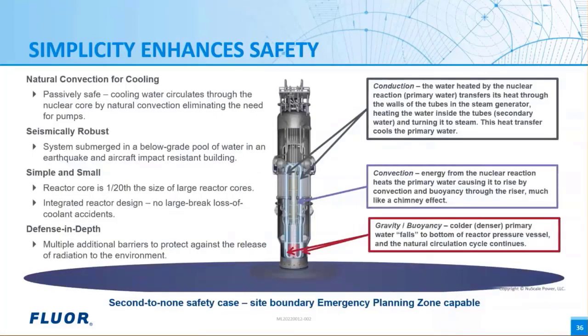So why is this reactor so safe? The safety is in the simplicity of the design. As I said previously, there are no pumps. It works entirely via natural circulation. The NuScale small modular reactor is classified as passively safe since it relies just on the laws of physics and heat transfer, specifically gravity, buoyancy, convection, and conduction. So there are fewer moving parts and fewer systems to fail. It's robust because the reactor building is seismically robust and will withstand 0.5 g of peak ground acceleration.